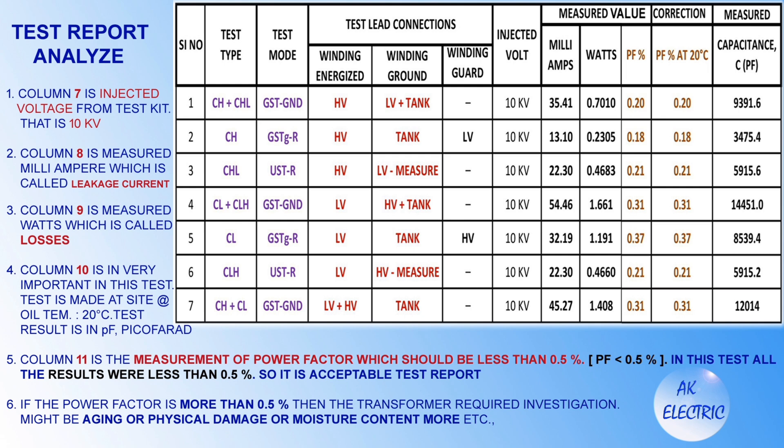Analyzing the overall test report: Column 7 is the injected voltage from the test kit — 10 kV. Column 8 is measured milliampere, which is the leakage current. Column 9 is measured watts, which represents losses. Column 10 is very important — the test is made at oil temperature 20 degrees Celsius, and results are in picofarad. Column 11 is the measurement of power factor, which should be less than 0.5%. In this test all results were less than 0.5%, so it is an acceptable test report. If the power factor is more than 0.5%, the transformer requires investigation — it might indicate aging, physical damage, or excessive moisture content.